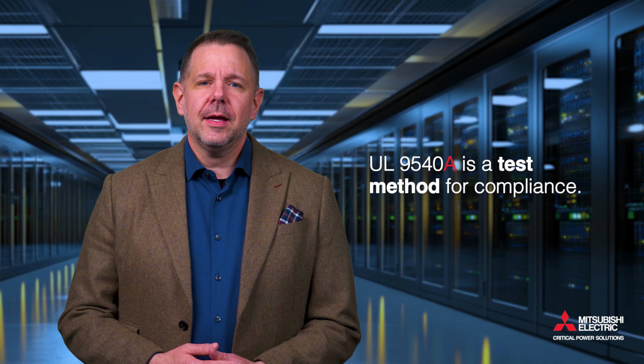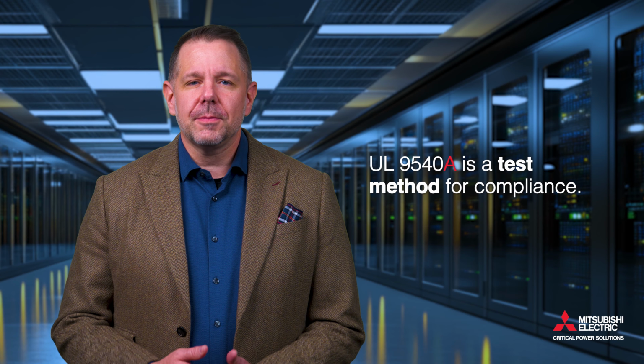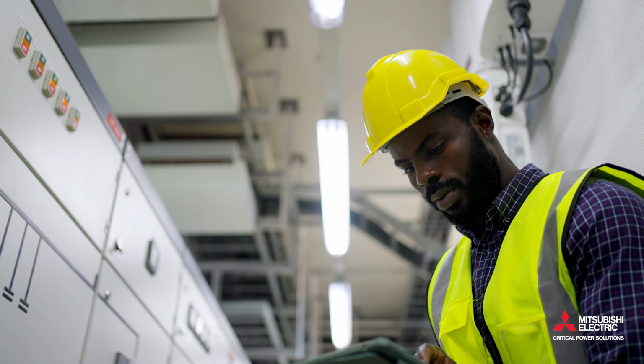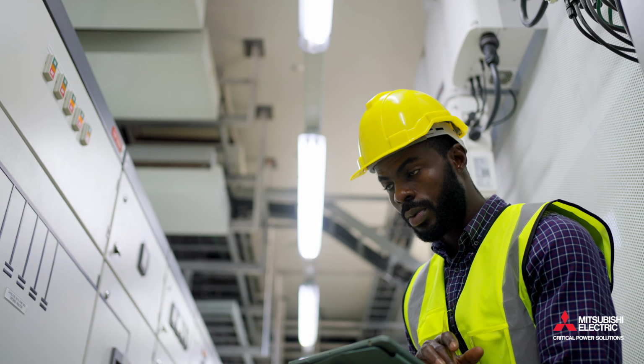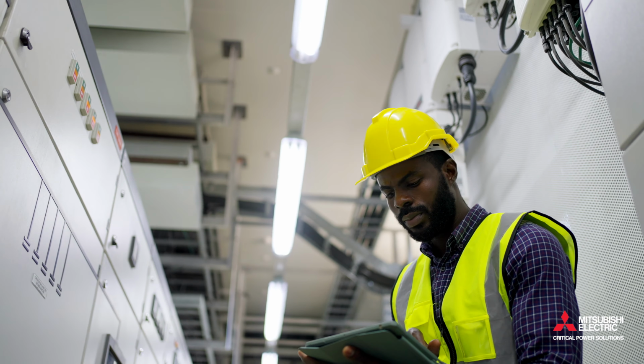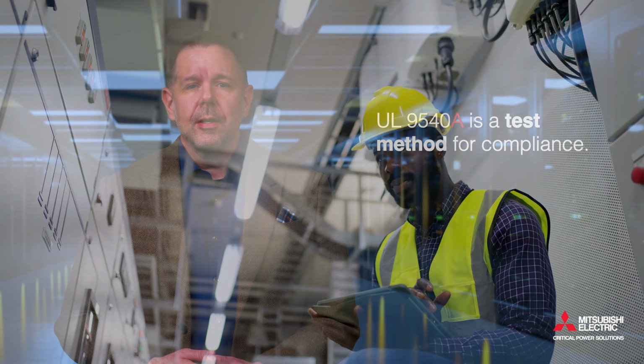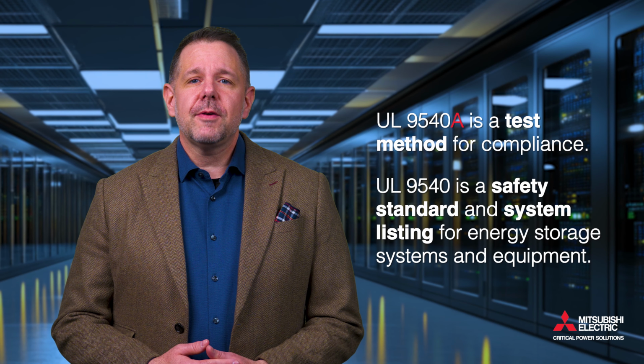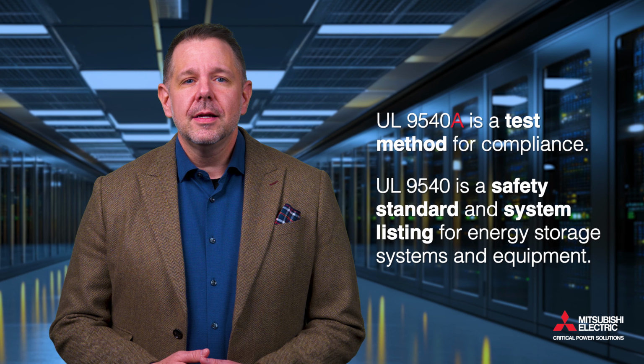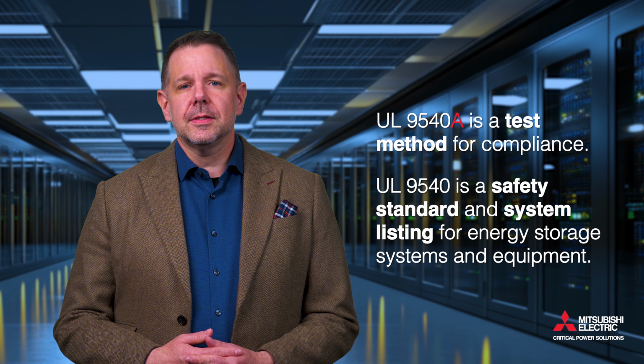I can tell you UL did not do the industry any favors by naming them so similar. First, it is important that we understand UL 9540A is merely a test method for compliance. It is performed on technologies to understand the thermal properties and evaluate thermal runaway, fire propagation of a product or energy storage system. On the other hand, UL 9540 is a safety standard and a system listing for energy storage systems and equipment.